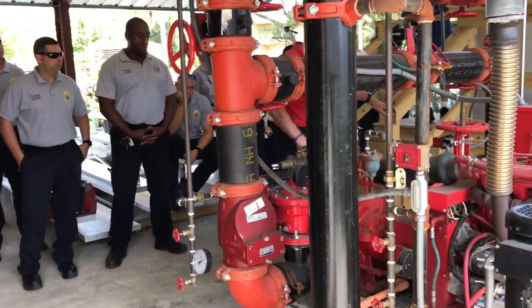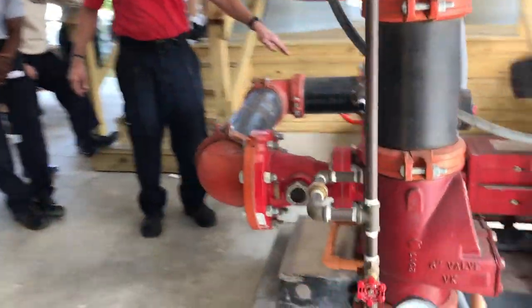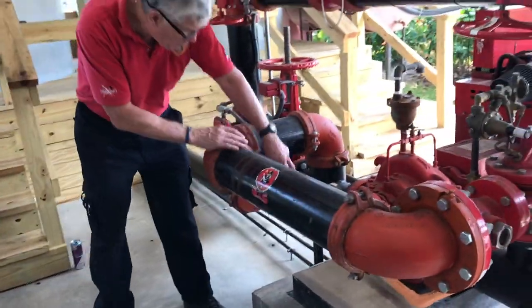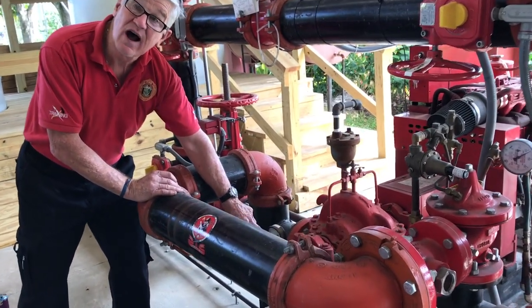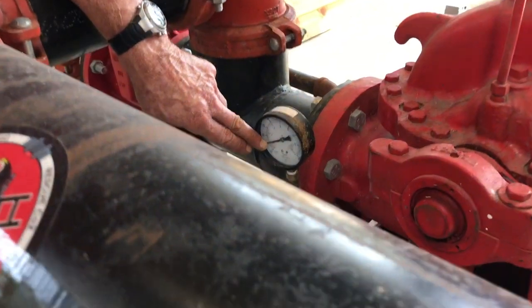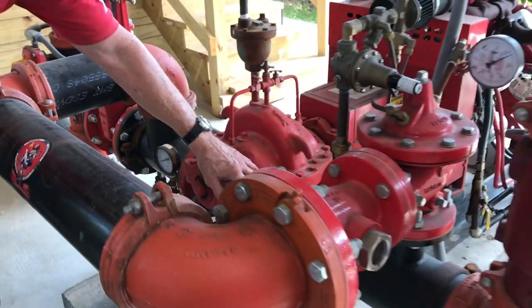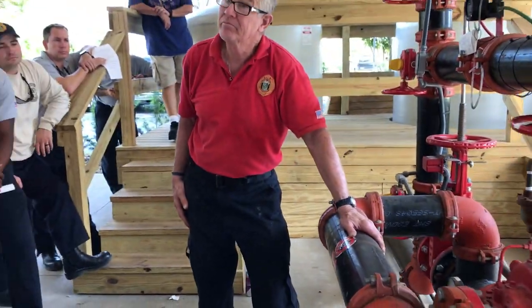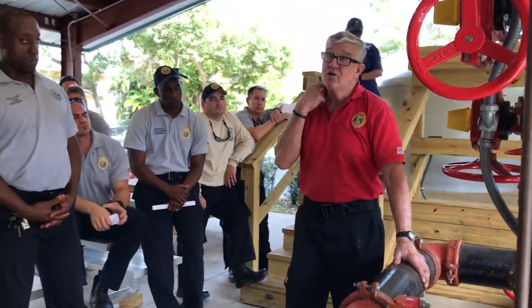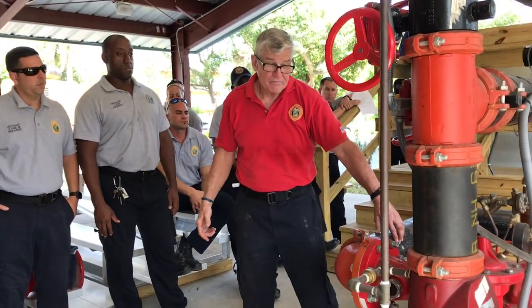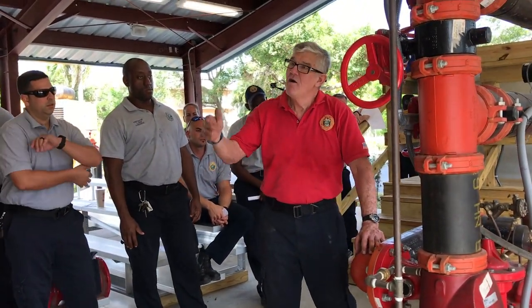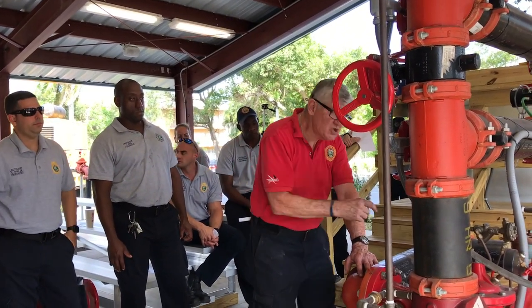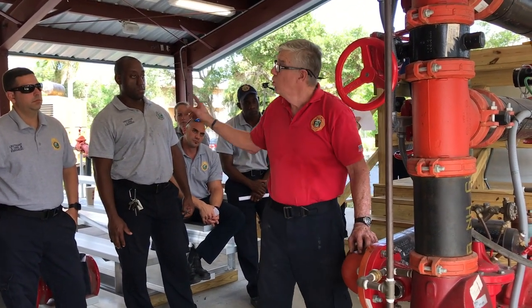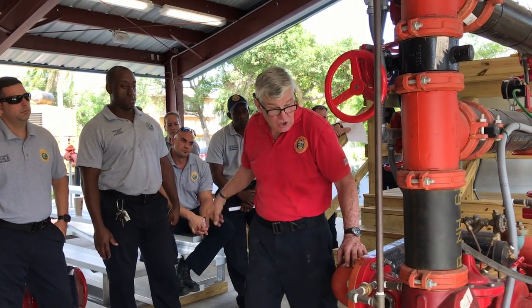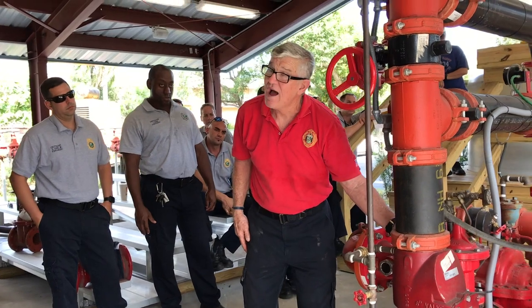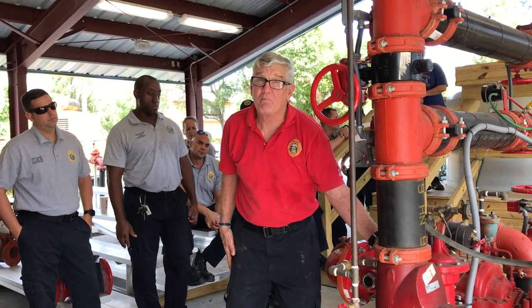City pressure would come into the system here. If this was Miami-Dade County, we'd be reading about 70 psi static city pressure. When the pump kicks on, this generates about 125 psi into the system. Think back to pumping the fire department connection. If you pump at a pressure over what this pump can produce, open the check valve on the fire department connection, and you will close this check valve on the side, the discharge side of the pump.